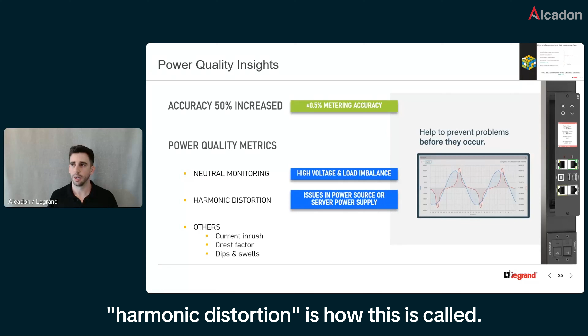So we thought, where's the best place to measure harmonic distortion? We concluded it should be at the very end of the power chain, the last interface before reaching your IT servers. By measuring harmonic distortion in the PDU, you get a clear picture of how much power is being dissipated as heat, so you can take corrective actions.